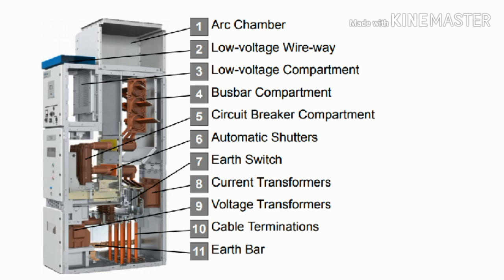Third is the low voltage compartment on the front side of the switchgear panel at the top. Here we place the protection relays and controlling switches like on and off, ammeters, voltmeters — all these low voltage components are fixed here.